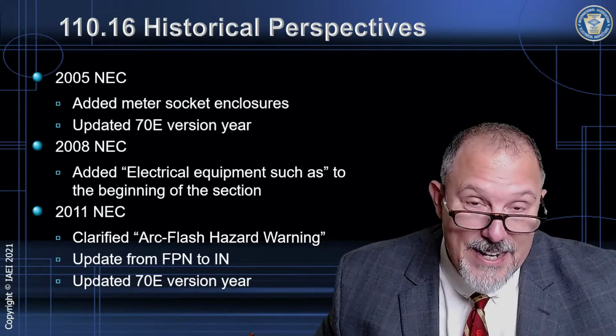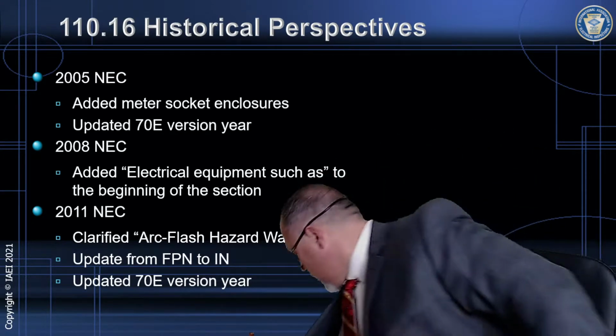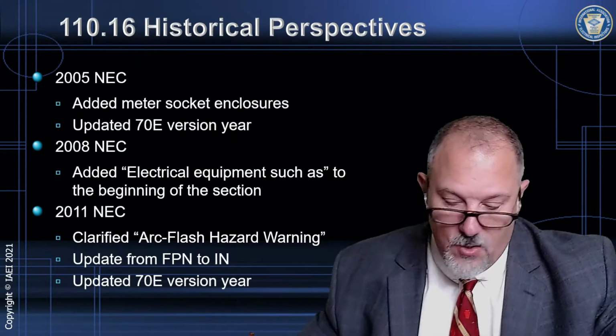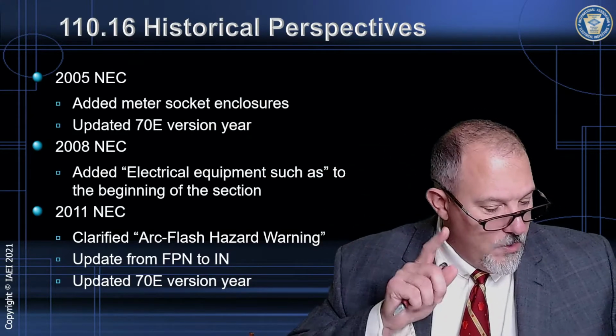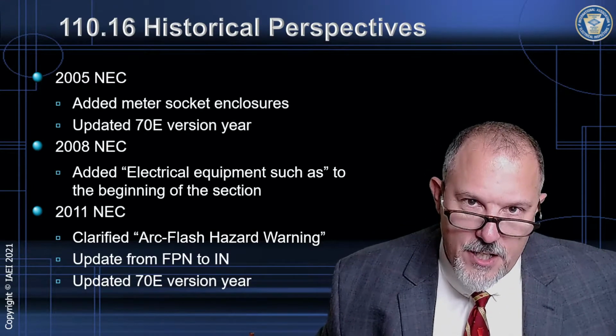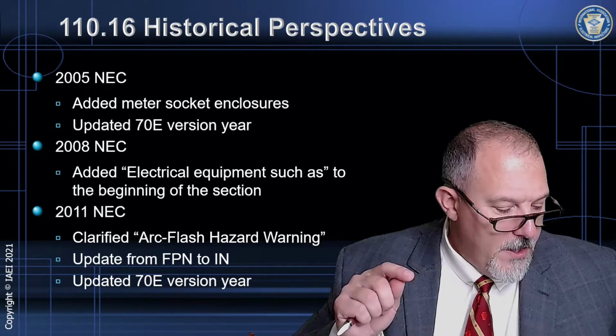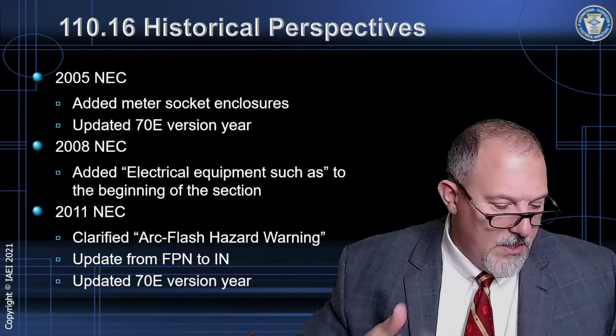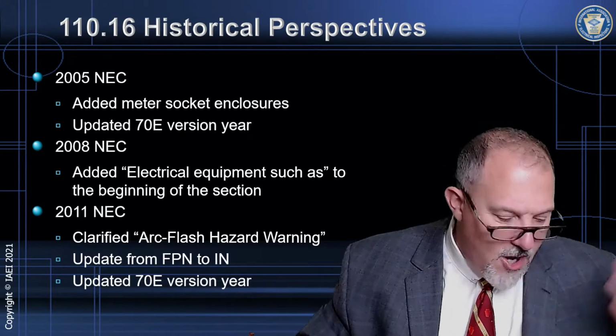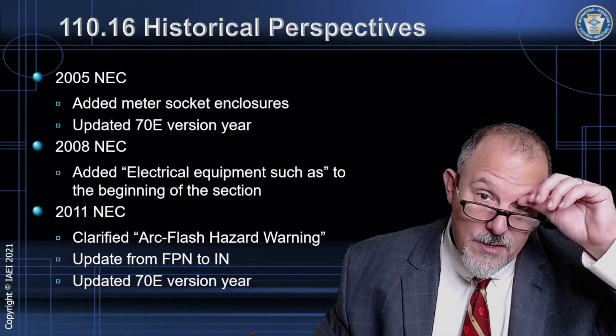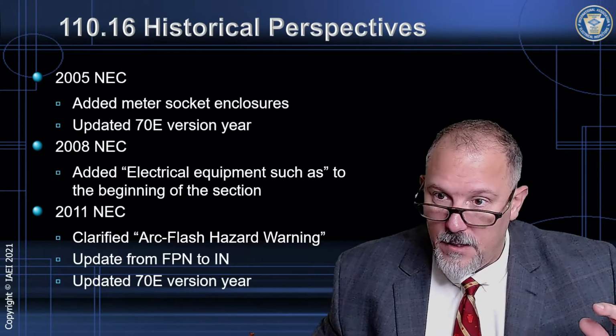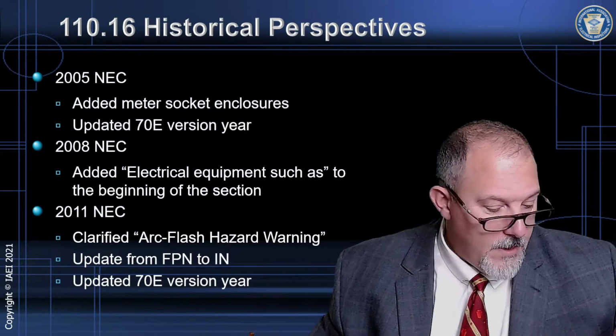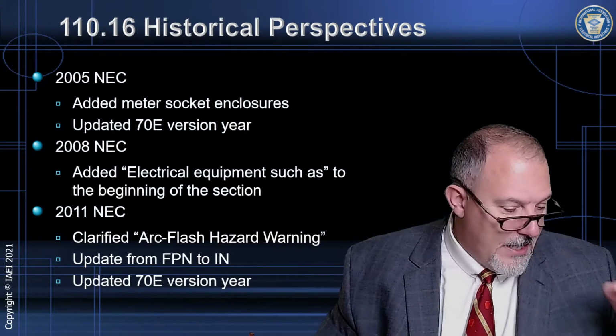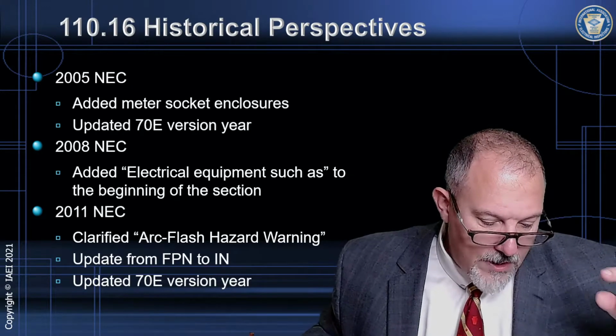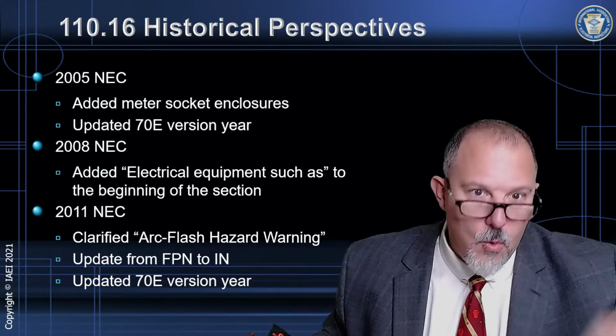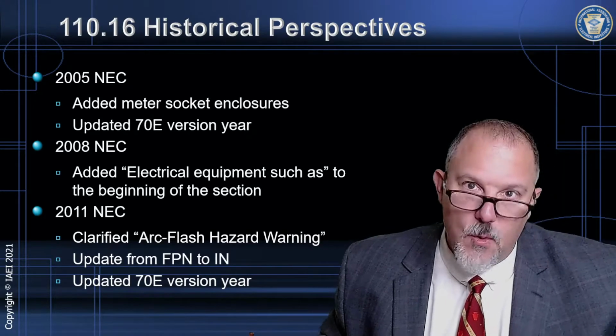We changed the title. What was the title before? 110.16 was titled Flash Protection. So 110.16 up until the 2011 version was not what we know it as today. It was flash protection, and in the 2011 version, it went to arc flash hazard warning. And that's what we live with today.